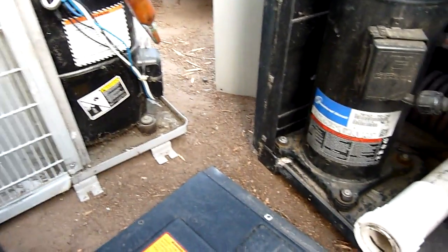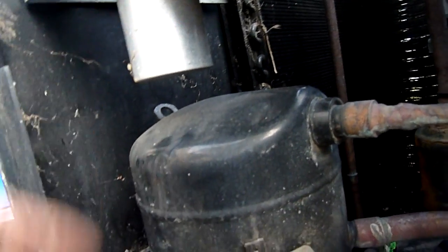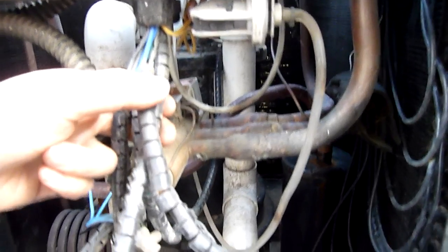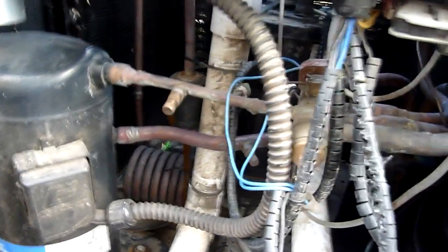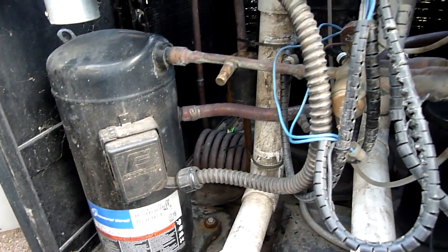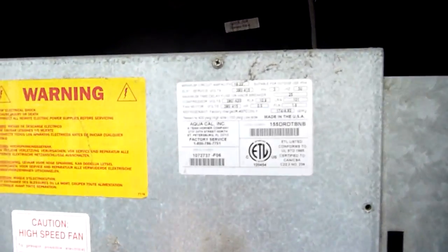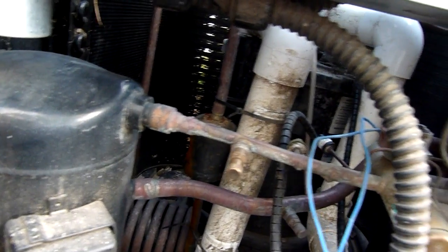Titanium heat exchanger, Copeland scroll compressor. I'm curious as to what that big cap's for — it's a 3-phase compressor, so why is there a giant run cap in there? Unless that's for the fan motor, which is unusual, since it's not a very big fan. You can see that wet patch down there — there's a big split in the side of that chiller drum. That's rather unfortunate. They spent lots of money making this thing work, even from new, but it never worked properly from new, and it was replaced with a cheap Chinese unit which excelled at its job. Kind of sad. They changed the reversing valve, changed the TX valve, regassed it a couple of times after breakages. It's just been a piece of junk from day one, which is unfortunate because I usually like American stuff, but this thing has been an absolute piece of shit. So this was its final death rattle, rupturing the heat exchanger drum.